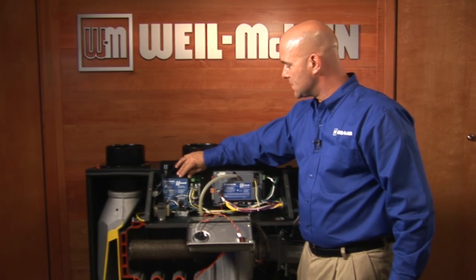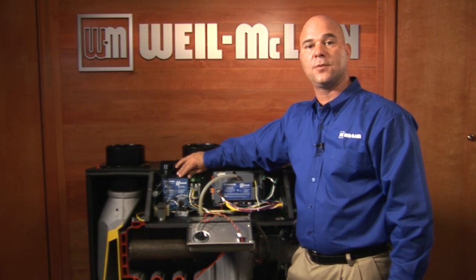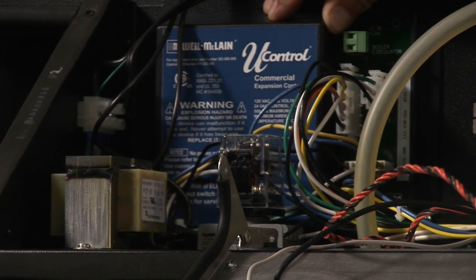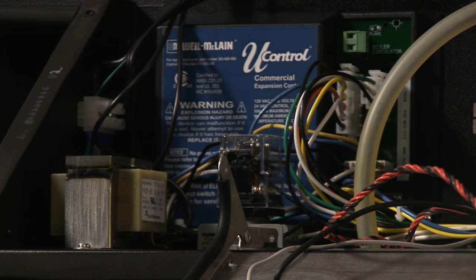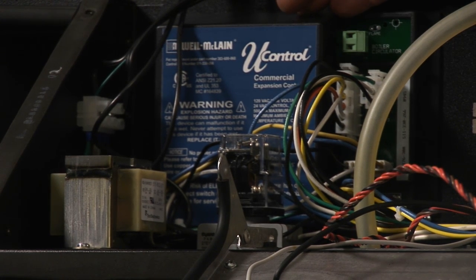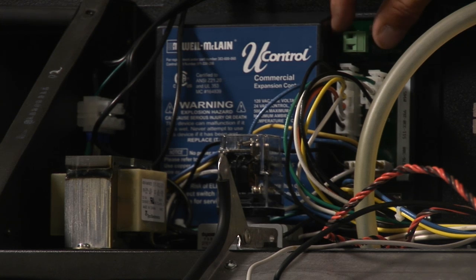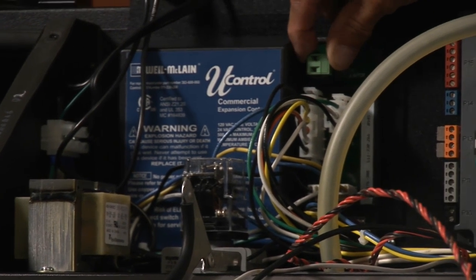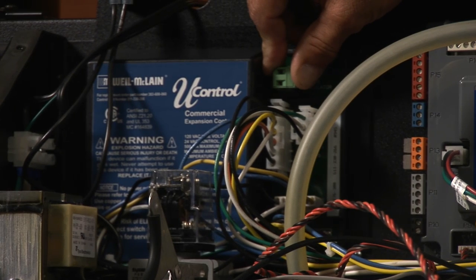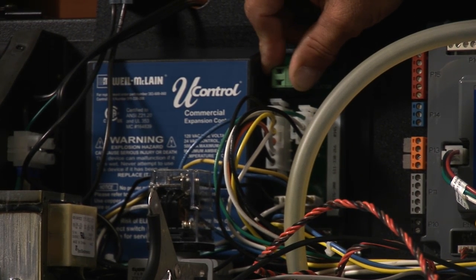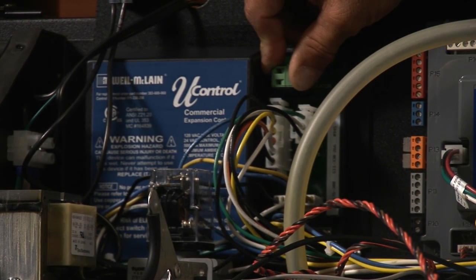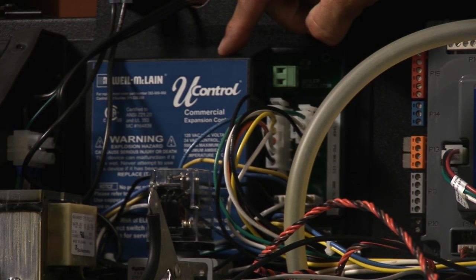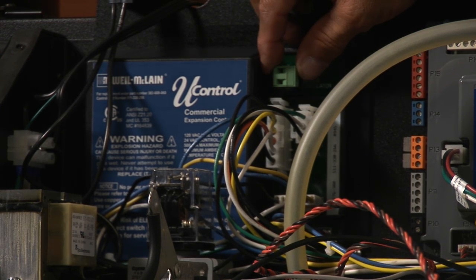This is different. This is added to the commercial model. This is what we call an expansion module. This expansion module basically eats up additional amperage that the larger boiler uses. There is a green connector right here. This is for the 4th pump outlet. The boiler itself can handle 3 pumps up to 2.2 amps each. This expansion module handles the boiler pump, which is up to a 10 amp pump.